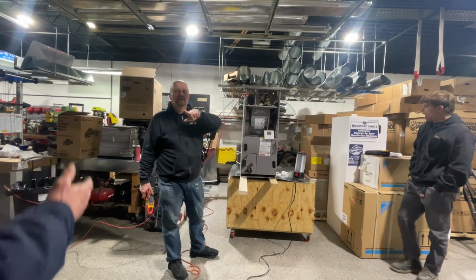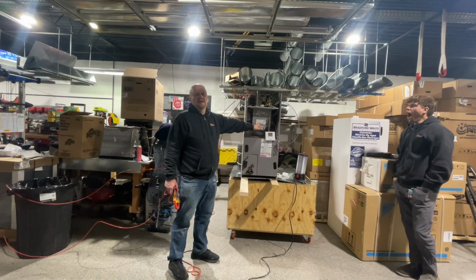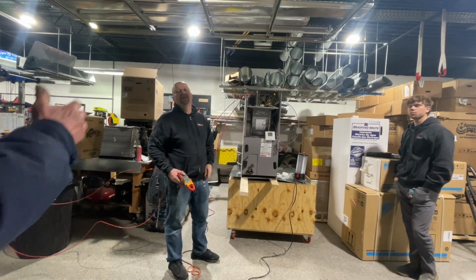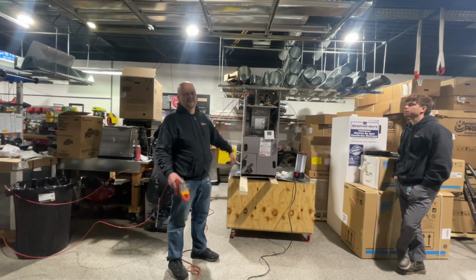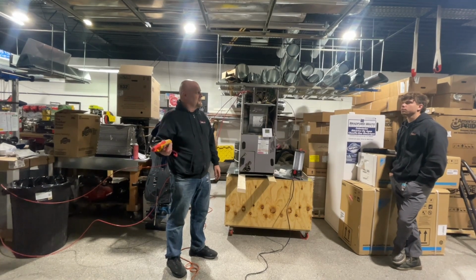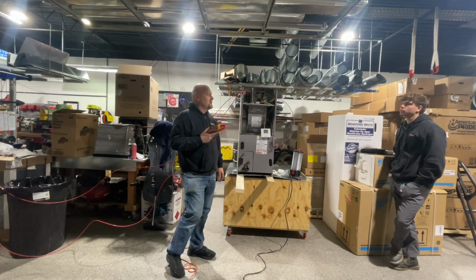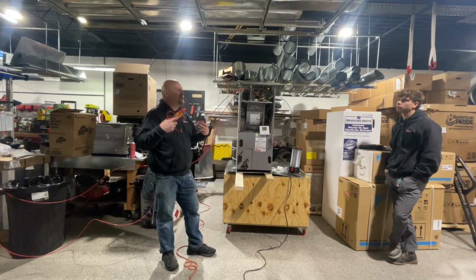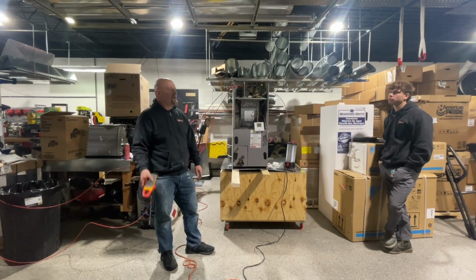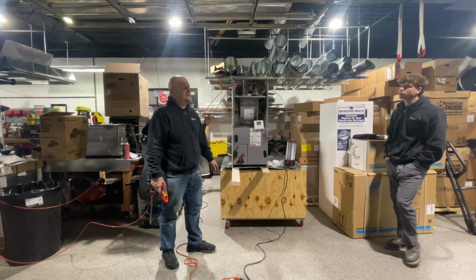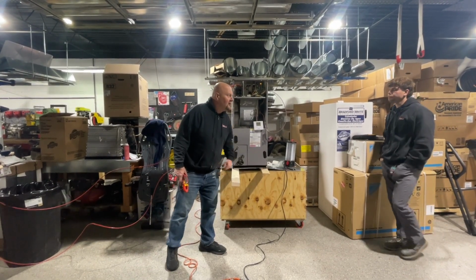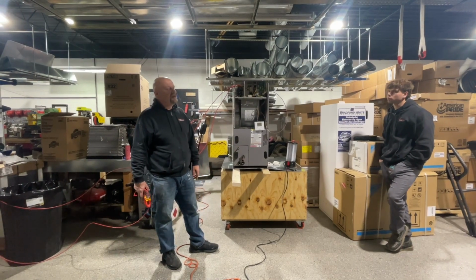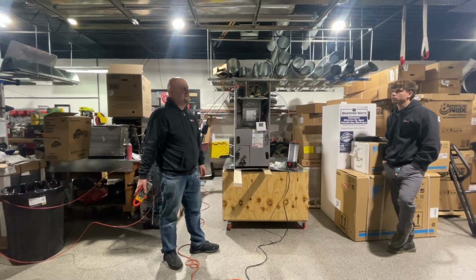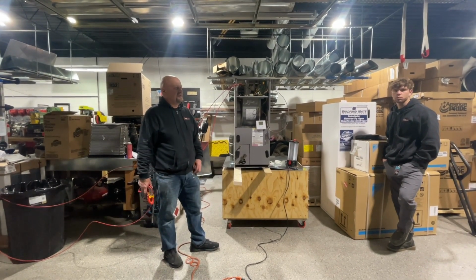This is an ECM motor, but it's easy start, whereas the other one's surge. Correct. And that's on any electrical equipment. If you start tripping circuit breakers, that means you're drawing too much power. There's a problem with the machinery. The motor's older, these are getting weaker. The electric strips, the compressor is overloaded. That's why it trips. You get it?